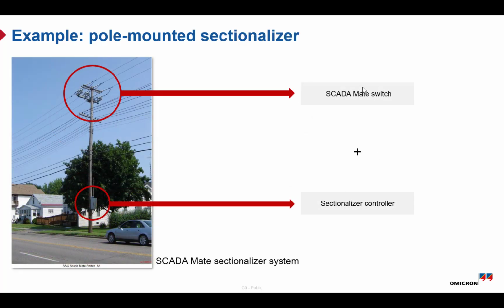The second example is the pole-mounted sectionalizer. At first look, it looks similar to a recloser, but there is one key difference. Instead of a vacuum circuit breaker, a sectionalizer uses a simple switch or disconnector. This means it cannot interrupt the fault current. So how does it work?